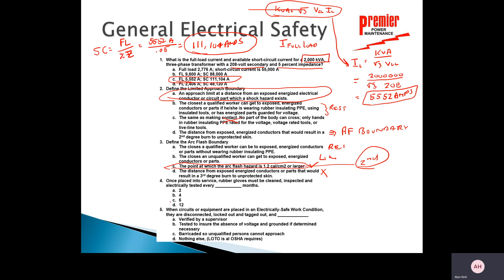Once placed into service, rubber gloves must be cleaned, inspected, and electrically tested every six months — that's the answer. And no more than 12 months from the date stamp on the cuff. So even if they sit in the bag and have never been issued, after one year they must be retested. Six months after the date of issue, but no more than 12 months after the date stamp.